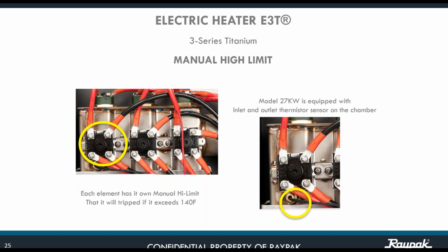Okay, also the manual high limit. Each element has its own manual high limit that will trip if it exceeds 140 degrees in temperature. We're going to see it in the next section, but let's advance on that one. Anytime that you have lack of water, improper water flow, chances are that that particular high limit will trip. So just reset it on top, but you need to find out what is the cause of the situation that is causing the high limit to trip off.